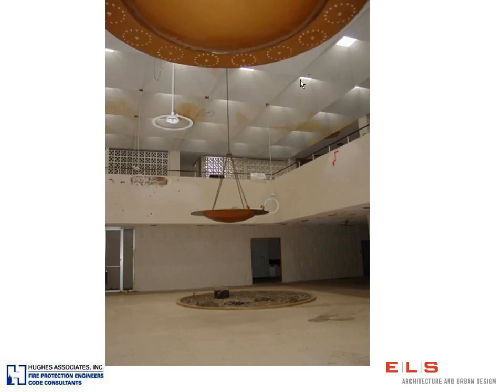One, the first thing we looked at was, well, can we put sprinklers up at the top of these boxes where the skylight is and make it effective? And what happened is that the walls of these boxes actually obstructed the spray pattern completely, so we would have had to have ended up with a sprinkler in every single box in this space, so that wasn't going to work. So then we wanted to explore putting sprinklers somehow on the underside of the ceiling. But then the challenges that we were faced with were the fact that these very, very large planters were creating an obstruction to the spray pattern. So that was causing us a problem, as well as how do we make the aesthetic work in this space so that the sprinklers are not an obtrusion to the character-defining features.